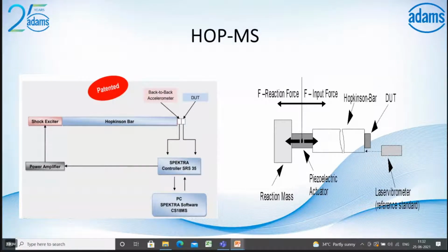So the same Hopkinson method. You will be giving a driving voltage to the exciter. The piezo exciter, which is stacked, will give, due to the reaction mass, the reaction force according to Newton's second law. The same force will be applied to the Hopkinson bar. Both the Hopkinson bar and the exciter are mounted on the same aluminum bar. So the propagation and reflection of waves generate the shocks, and you are able to measure the shocks for the calibrations.